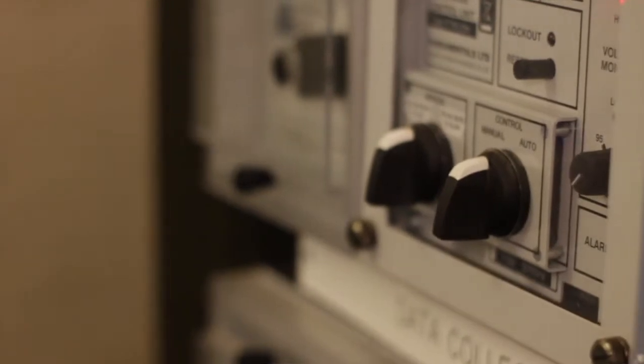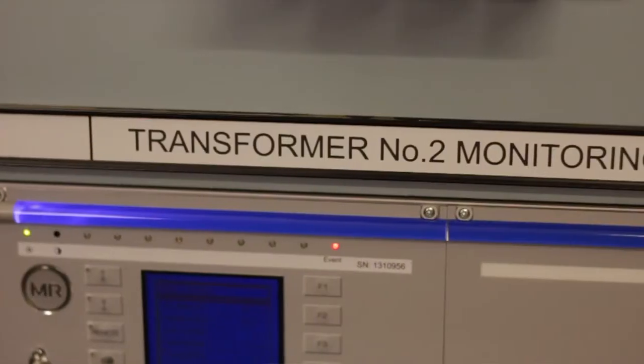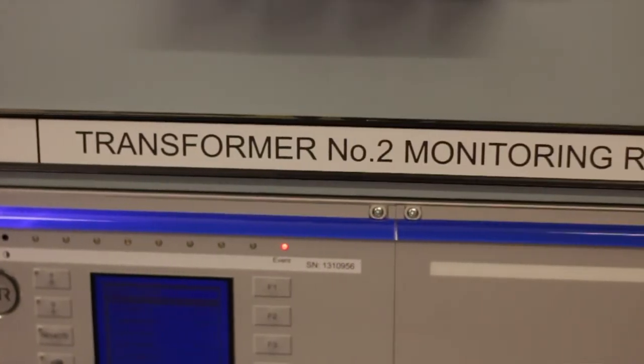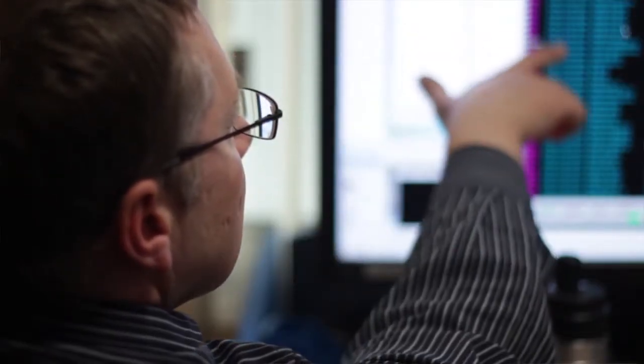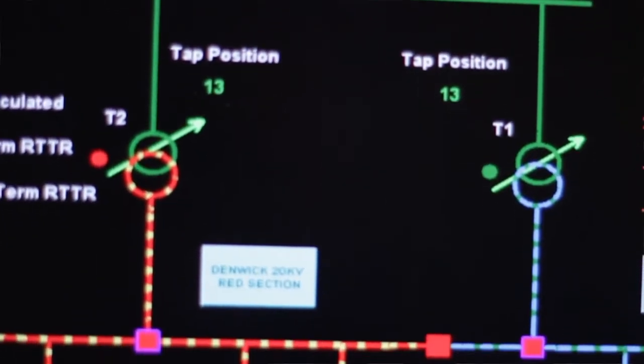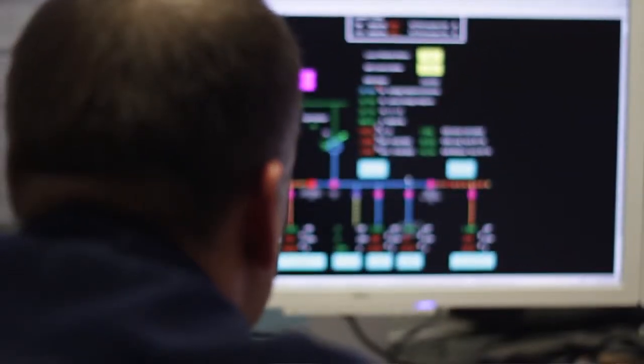But the really big step, and this is where wide area controllers like Gus come into their own, is saying we're going to raise our gaze. We're going to lift our eyes from staring at our feet to look out to where the customers are. With our new technology, we choose to also measure outgoing feeder current measurements and incorporate that into the decision making for when to operate the tap changer and therefore influence network voltages. That was used mainly as a monitoring tool to enable Gus to make its decisions.